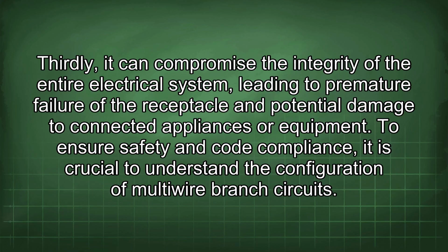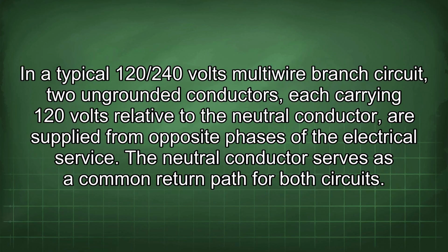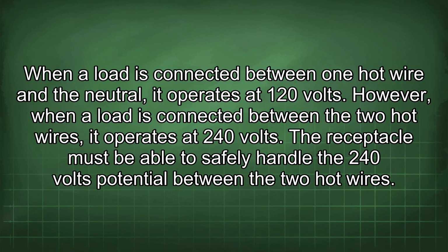To ensure safety and code compliance, it is crucial to understand the configuration of multi-wire branch circuits. In a typical 120/240 volts multi-wire branch circuit, two ungrounded conductors, each carrying 120 volts relative to the neutral conductor, are supplied from opposite phases of the electrical service. The neutral conductor serves as a common return path for both circuits. When a load is connected between one hot wire and the neutral, it operates at 120 volts. However, when a load is connected between the two hot wires, it operates at 240 volts. The receptacle must be able to safely handle the 240 volts potential between the two hot wires.